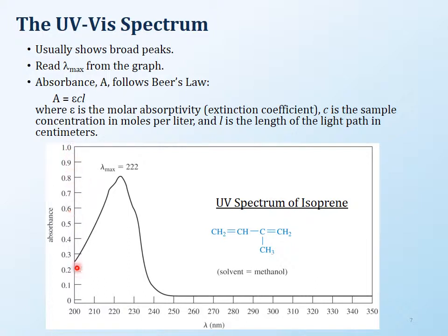So the absorption scale is the one that you really have to mind, because in case of IR, you didn't really have any issues. It was just transmittance. But in case of UV-visible spectroscopy, you have to be careful because the absorbance scale is very limited. Okay, you can go up to 10 also. But if your sample is too dilute, then you may not be able to clearly see the lambda max. And on the other hand, if it is too concentrated, then this peak will be so high up there that you don't really know where your lambda max is. Okay, and if it's too dilute, it will be way down here, and then you don't know what your lambda max is. So you really need to have a nice concentration of sample in there, and sometimes this takes a little trial and error, and then you figure out, okay, this is the concentration I need. So if you're looking at colored samples, then you try to make sure that you have some color in your sample, but that can be very deceiving also.